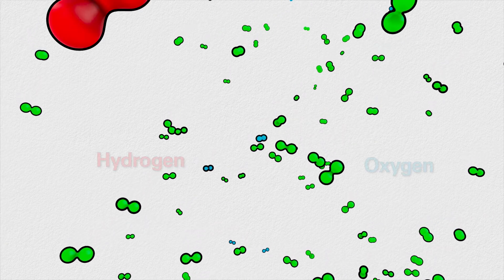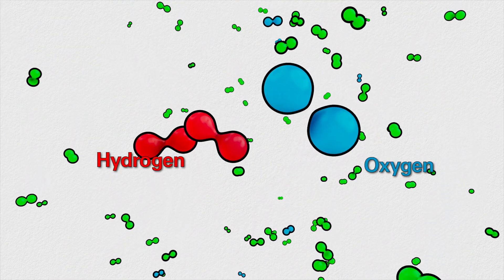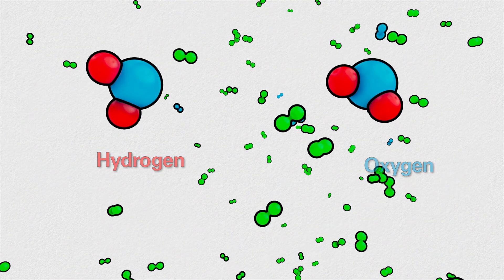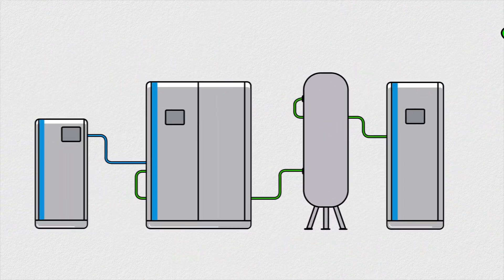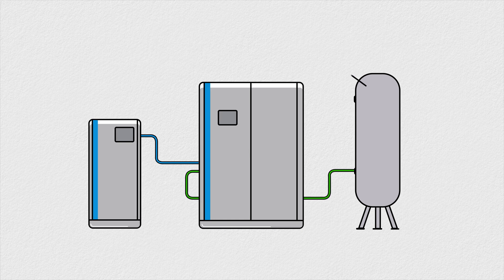Nitrogen gas purifiers typically rely on hydrogen. It reacts with the oxygen present in lower purity nitrogen, removing the O2 to achieve that very high purity. Without a purifier, nitrogen generation systems are not capable of producing this high purity nitrogen.